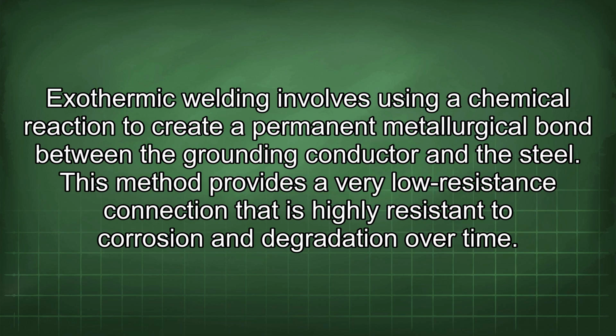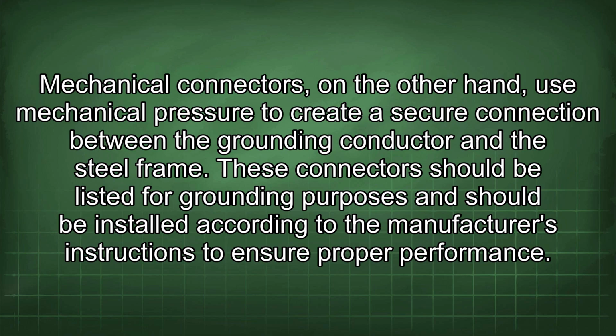Exothermic welding involves using a chemical reaction to create a permanent metallurgical bond between the grounding conductor and the steel. This method provides a very low resistance connection that is highly resistant to corrosion and degradation over time. Mechanical connectors, on the other hand, use mechanical pressure to create a secure connection between the grounding conductor and the steel frame. These connectors should be listed for grounding purposes and should be installed according to the manufacturer's instructions to ensure proper performance.